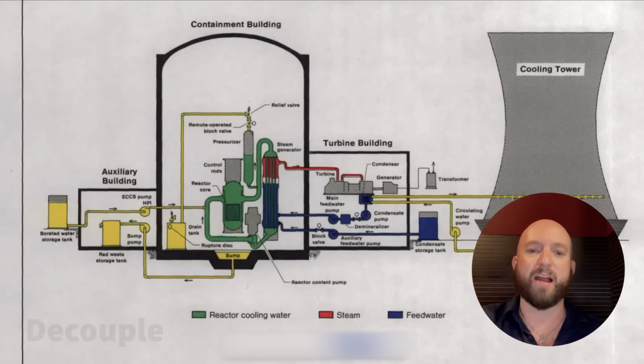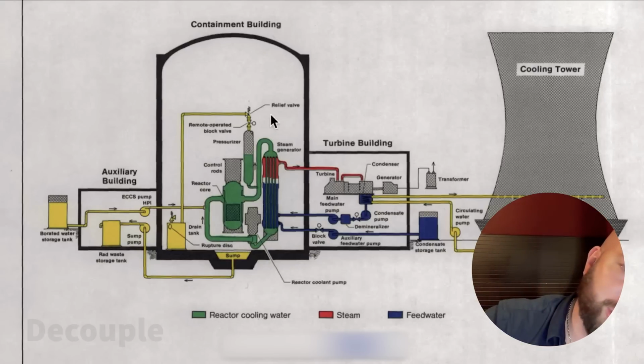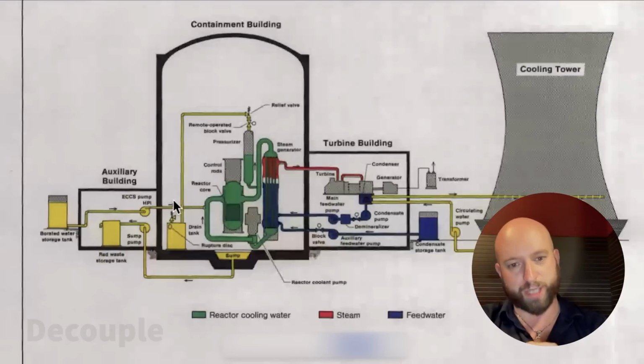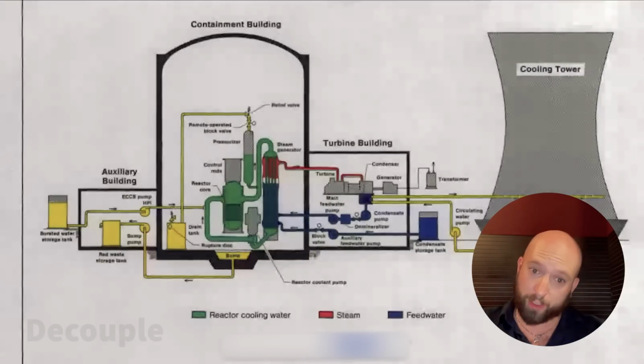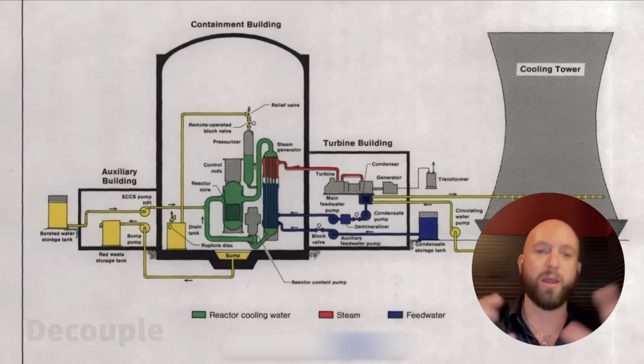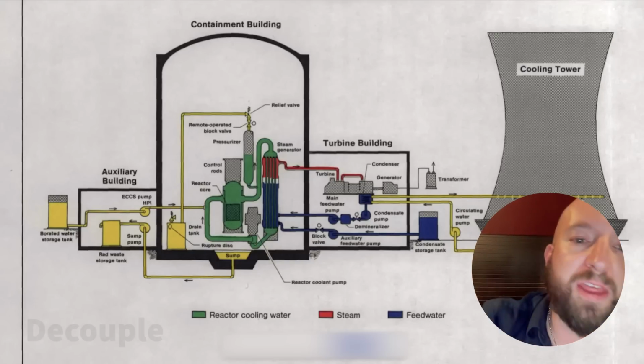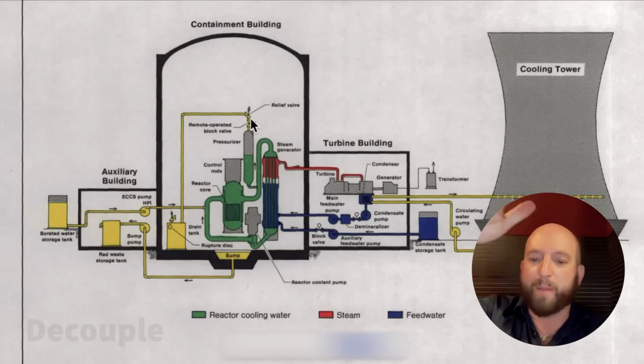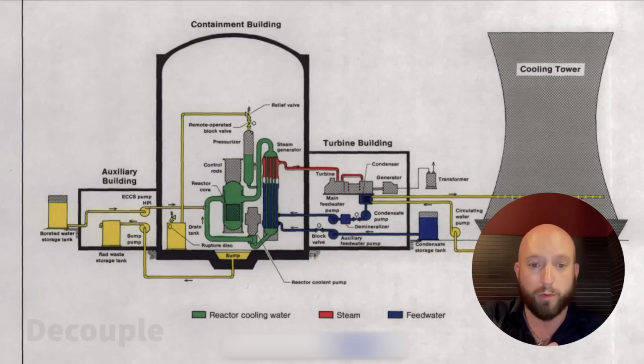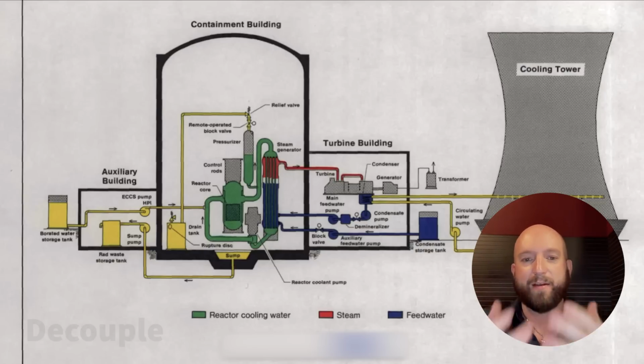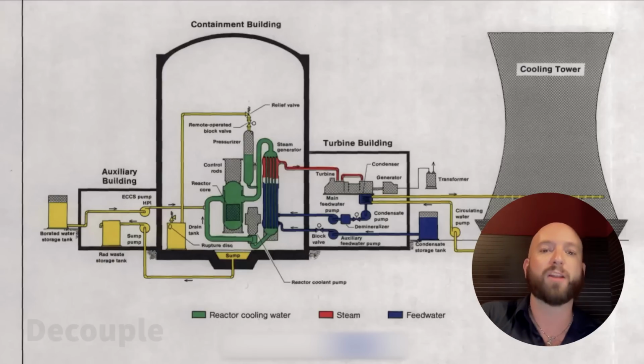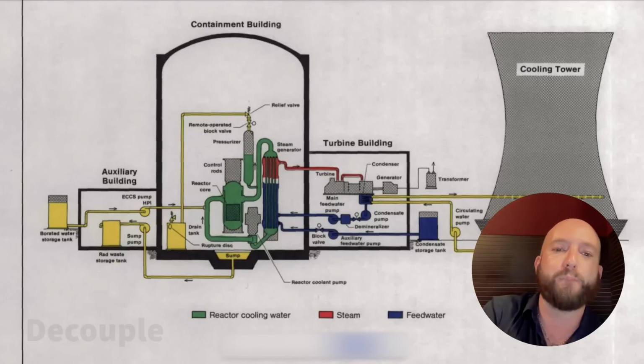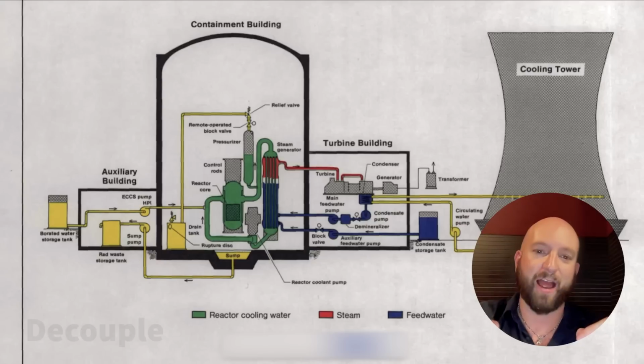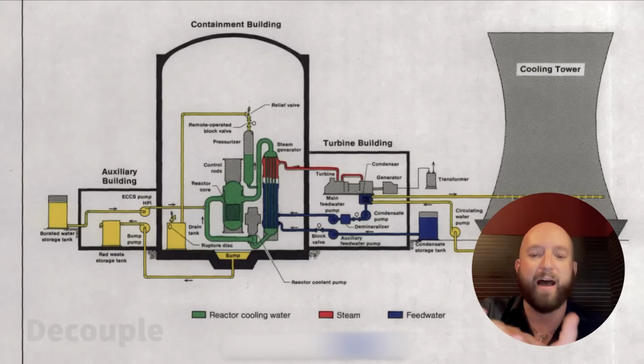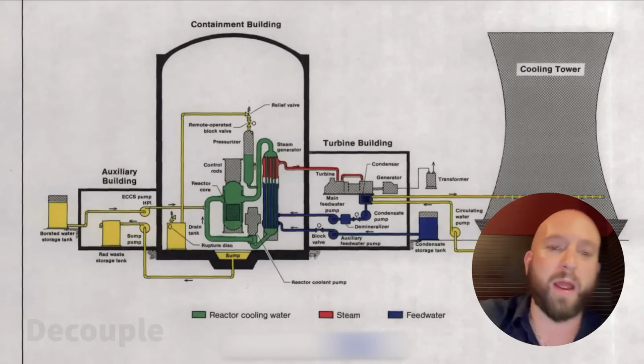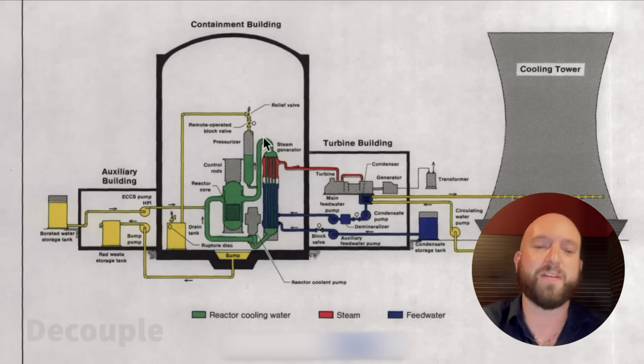But what happens is a couple seconds later, the reactor coolant system pressure starts dropping because the reactor is shut down, so we're no longer emitting that heat. The reactor coolant starts cooling down and shrinking, which is actually reducing the pressure even more. So the logic in the system basically says that pilot-operated relief valve should shut down, should close. And that's a solenoid-activated valve. And the logic works perfectly well. That PORV shuts down perfectly, and it's de-energized. The problem is there's literally a mechanical fault in that valve. That valve gets jammed open due to an error, essentially a fault actually in the design of this valve.